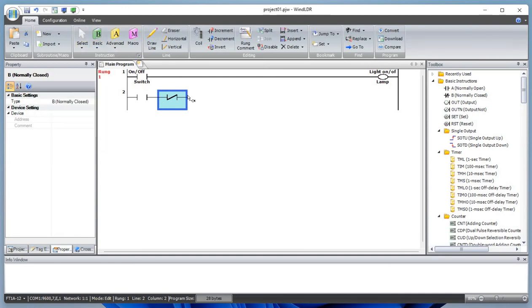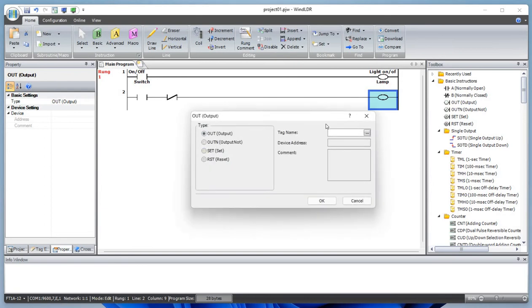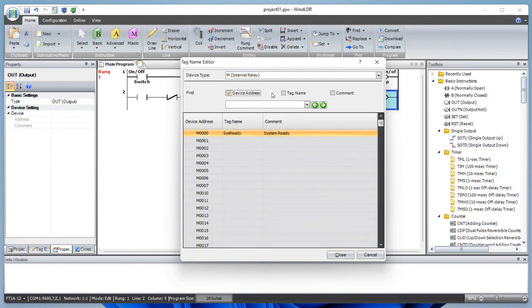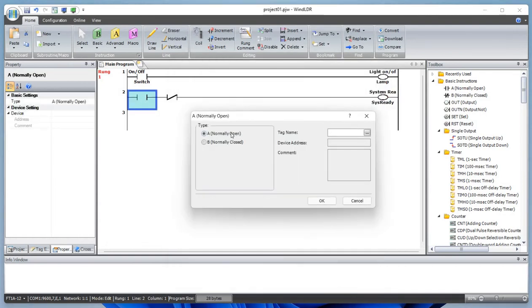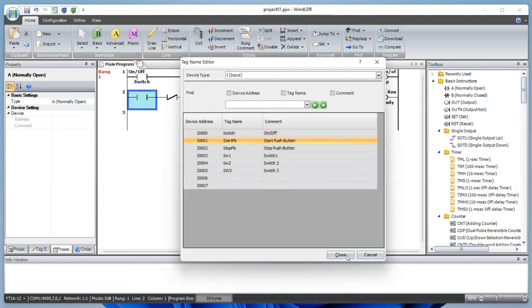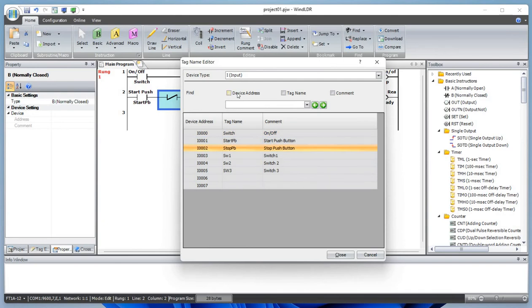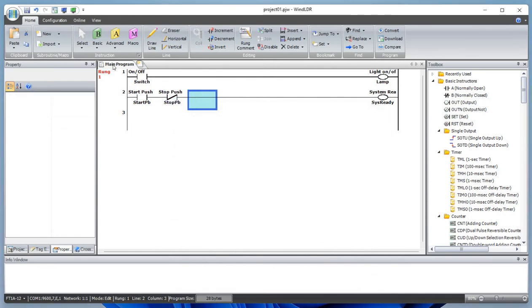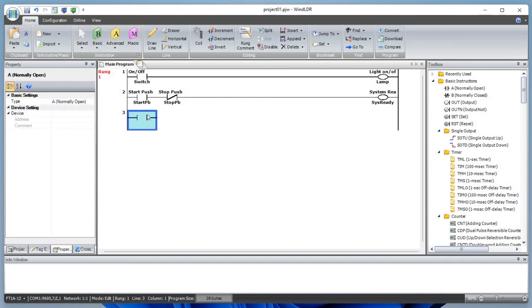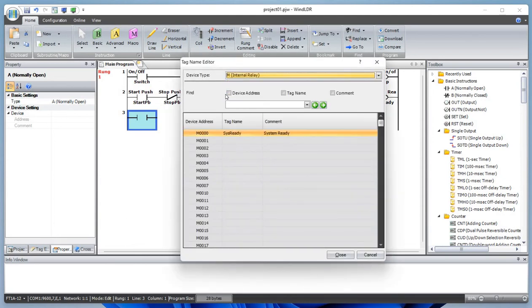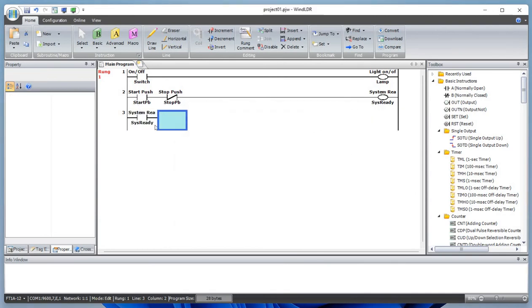Let's add a normally open contact for the start push button, and one more normally closed contact. Let's define this output as a memory bit because we are making a latching circuit — a self-holding circuit. This is our start push button on the enclosure. Let's also define our stop push button, which is also on the enclosure. This will be our internal memory bit and coil.